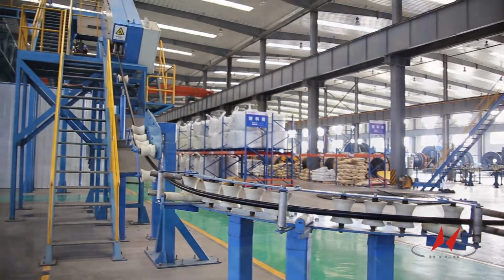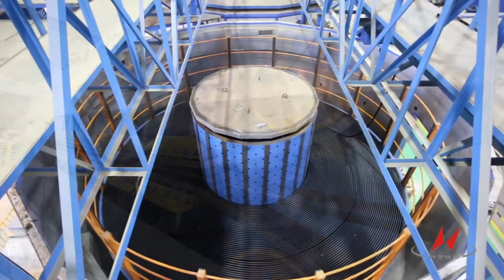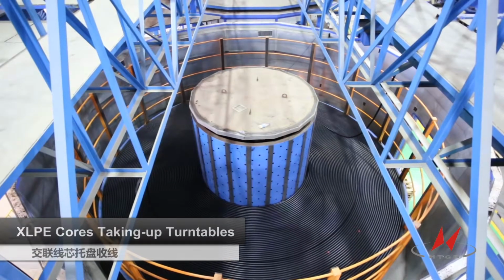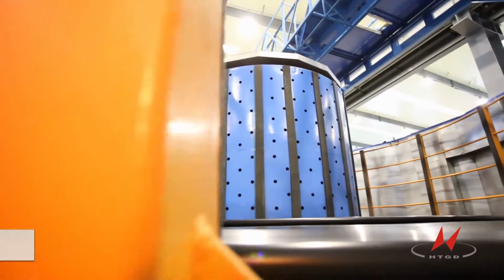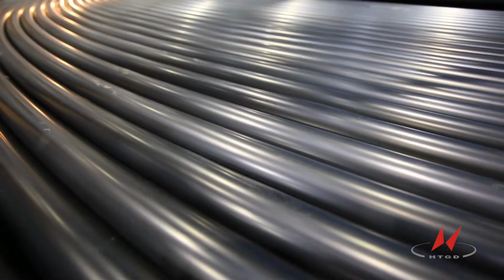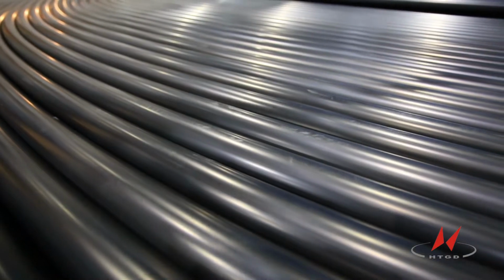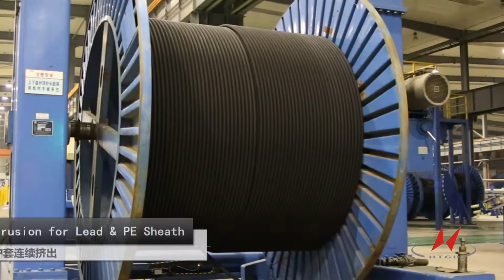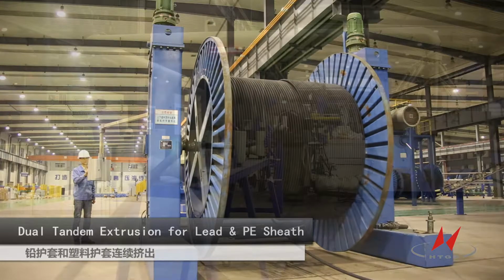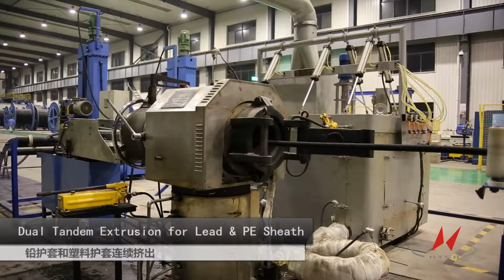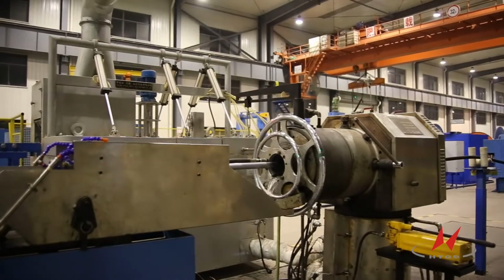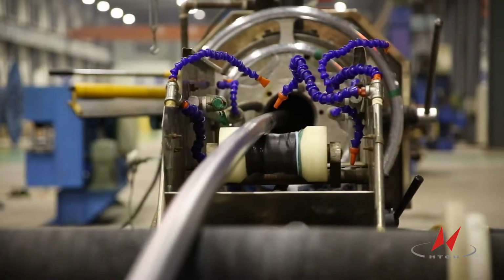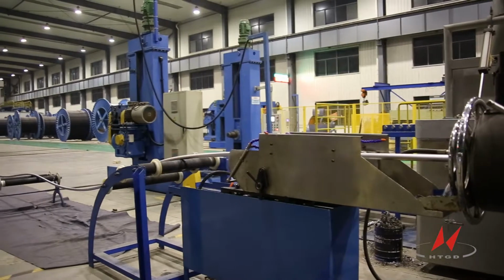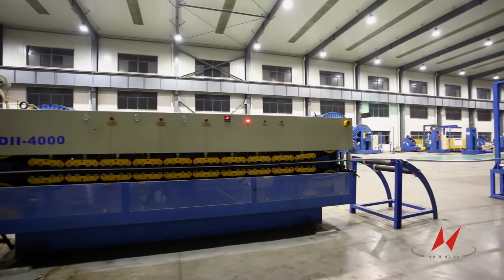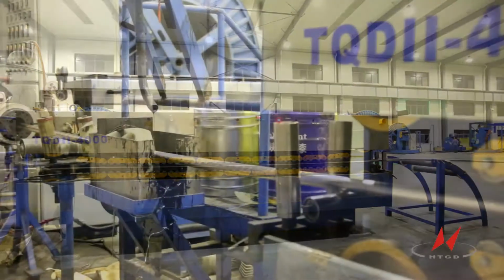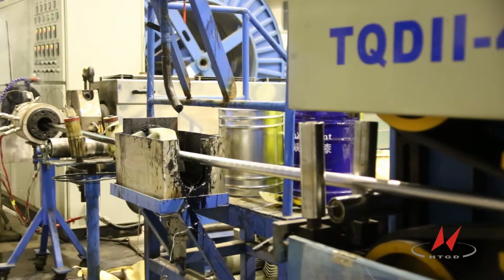The 8.5 meters online degassing chamber is developed and designed by the company itself. Insulation heating and degassing of submarine cable in the clean back-twisting turntable will make a full vulcanization on insulation and relieve internal stress. The company uses the newly developed continuous lead extrusion machine for lead sheath production, in addition to ultrasonic thickness metering to ensure the lead sheath thickness, and realize the continuous production of long submarine cable lead sheath, capable of producing lead sheath whose core diameter is 5 to 160 mm.